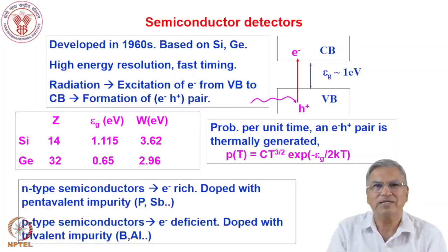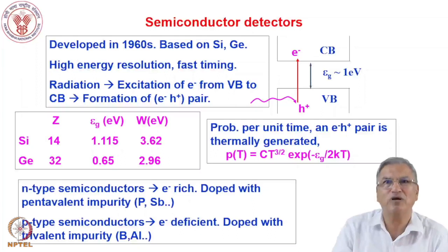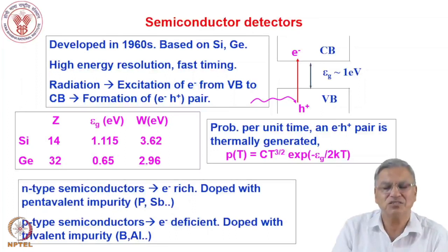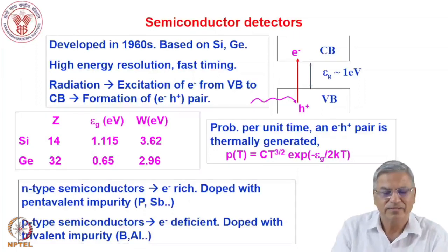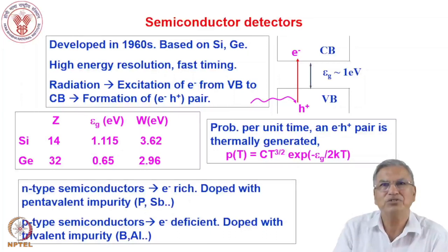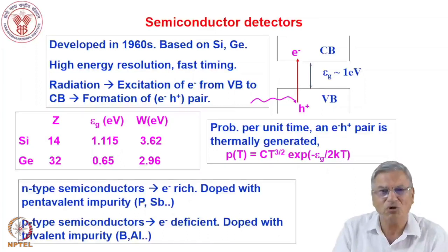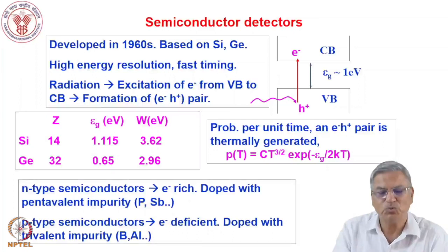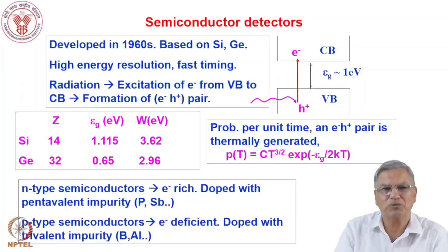Semiconductors are materials with a band gap range of around a few electron volts — they are between metals and insulators. These detectors were developed in the 1960s and are mainly based on silicon and germanium. They have excellent energy resolution and fast timing, though the detection efficiency for gamma rays is not that high because of the low atomic number of these materials — silicon is 14, germanium is 32. Overall, they are among the best detectors for gamma ray spectroscopy.